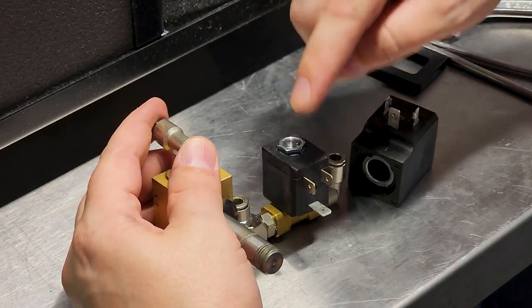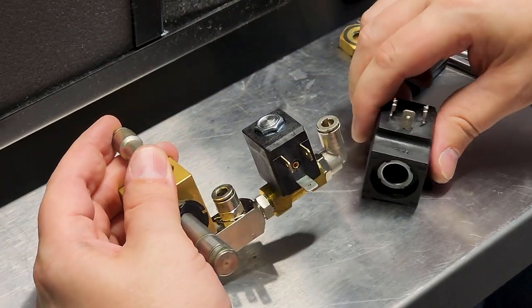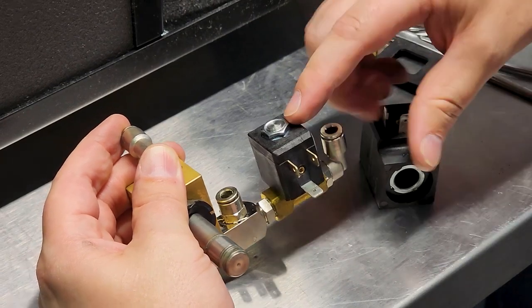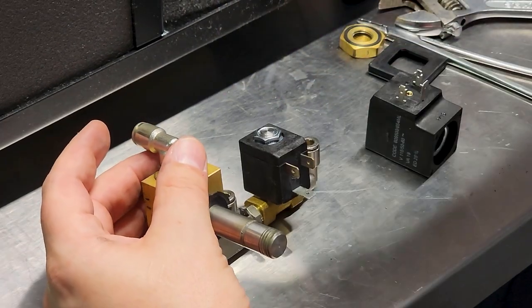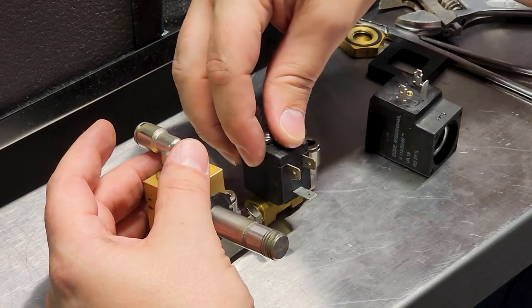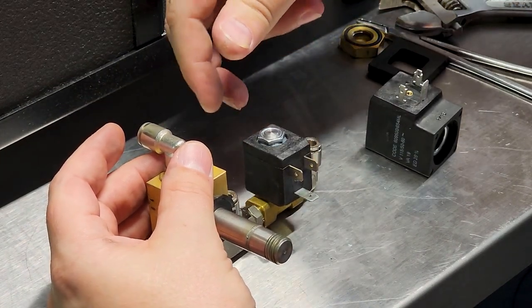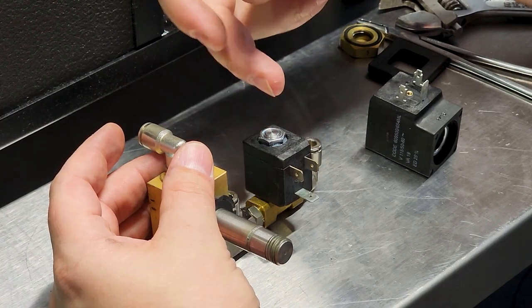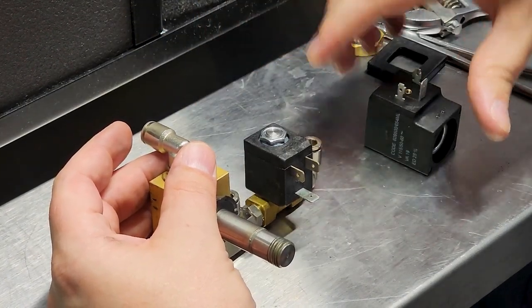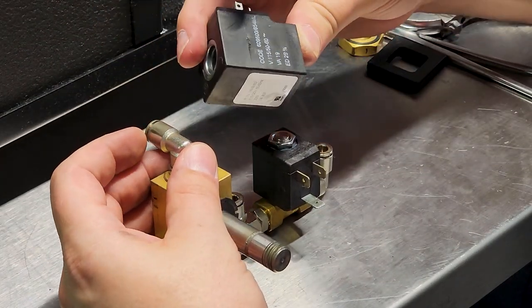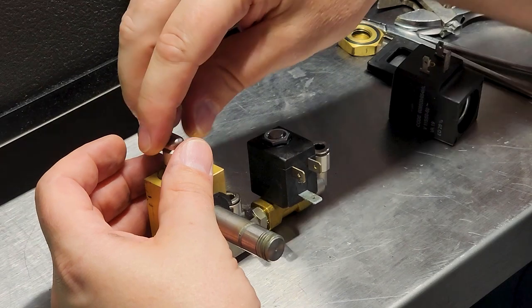This is a good solenoid, same voltage, and it just handles different pressure. There are various ways to rate solenoids. It's going to be rated based on its pressure, its temperature handling, and its input voltage that activates it. So there's a variety of things to consider. If you ever have to replace these, always try and replace them with an exact part number because if you don't, you will run into some problems like valve seal issues.